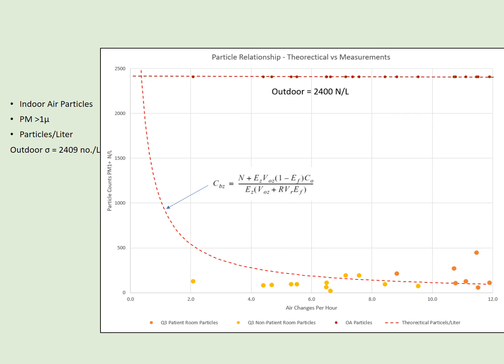And again, we have every reason to believe that by reducing ventilation rates, we will still be removing particles very effectively and efficiently. So ostensibly, we can reduce these rooms that are at 10 air changes down to 5 or 4 or 2, and we still expect to see this particle data looking very good, like healthy indoor air data.